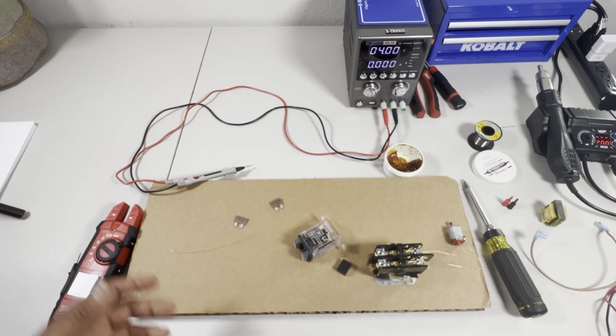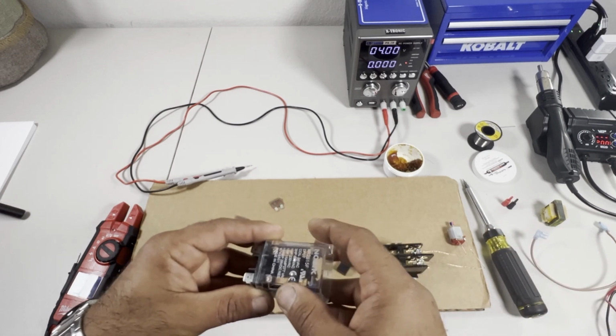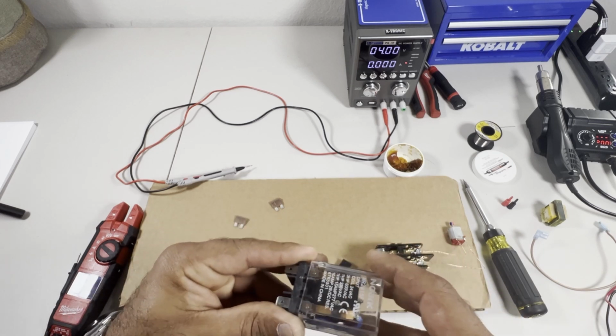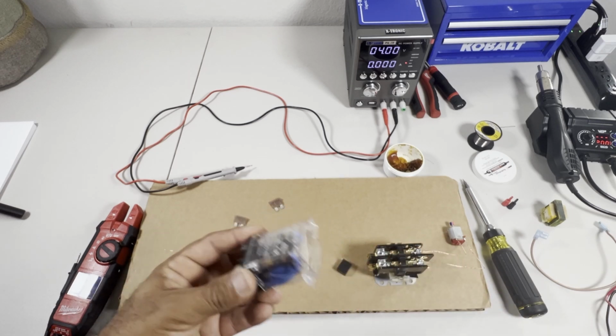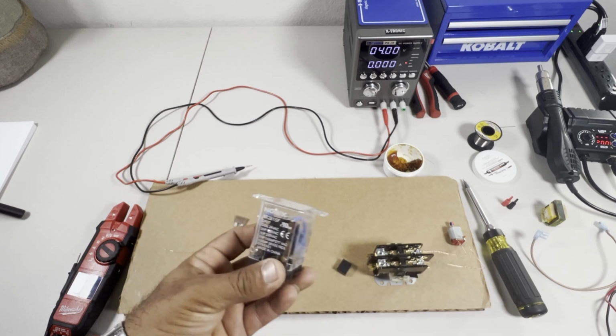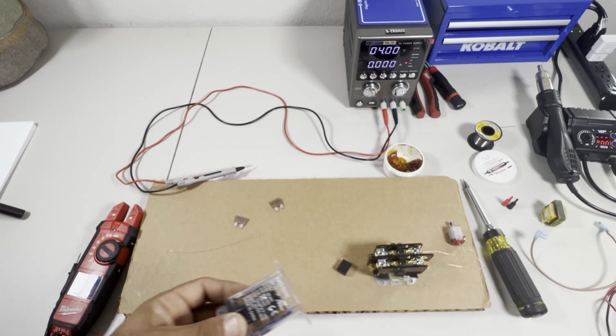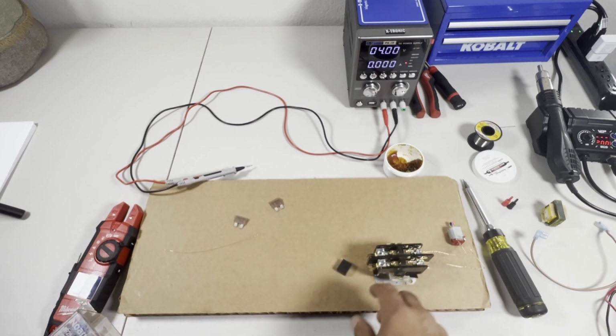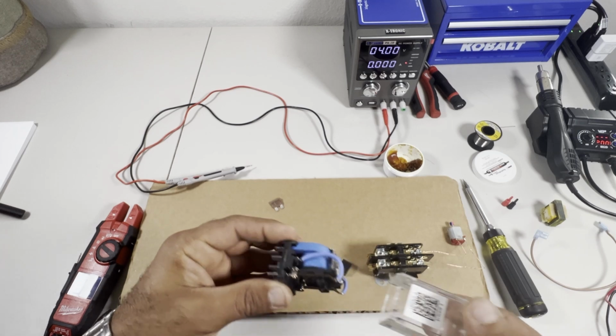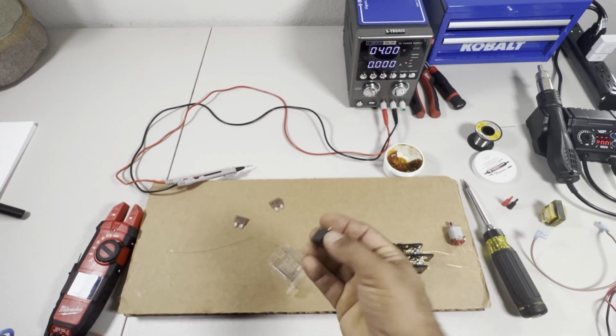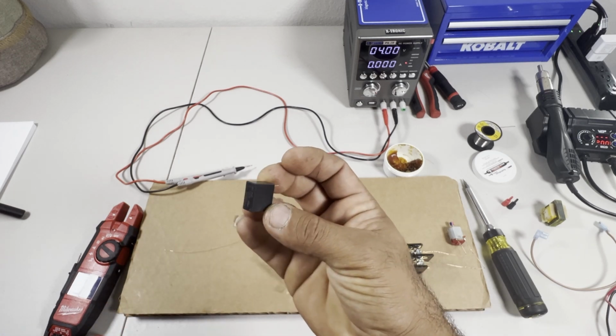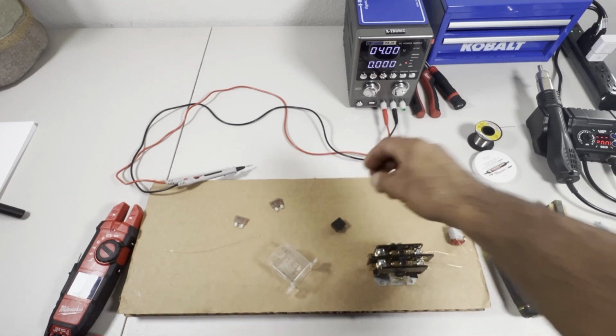Can control the high voltage equipment. Like we say, we have a control board and it works off of 24 volts or 3 volts or 5 volts. It doesn't matter. The controls never need a high voltage for operation. The controls are always going to be running on the low. Now, to be able to control components that are running on the high voltage, you're going to need relays. A contactor is a relay. Ice cube relay is a relay. These little bitty ones that you see on the control boards, they are relays.